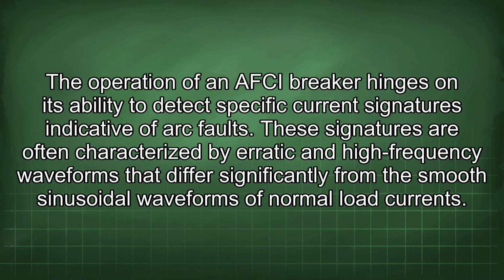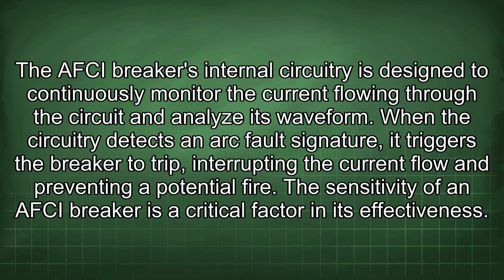These signatures are often characterized by erratic and high-frequency waveforms that differ significantly from the smooth sinusoidal waveforms of normal load currents. AFCI breakers' internal circuitry is designed to continuously monitor the current flowing through the circuit and analyze its waveform. When this circuitry detects an arc fault signature, it triggers the breaker to trip, interrupting the current flow and preventing a potential fire. The sensitivity of an AFCI breaker is a critical factor in its effectiveness.